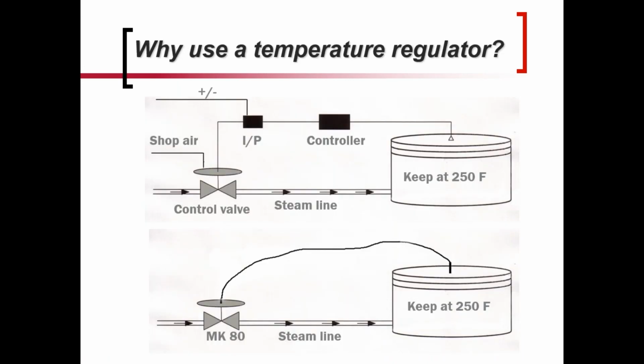So just to remind everybody here, the beauty of this is not only are you getting rid of all the parts and making this thing completely self-contained, but you're also getting rid of all the wiring. So if you're in a class 1 div 1 situation, a self-contained temperature regulator with a bulb and a capillary can be a much better value to install, and get very, very similar results, assuming the valve is properly sized and installed.